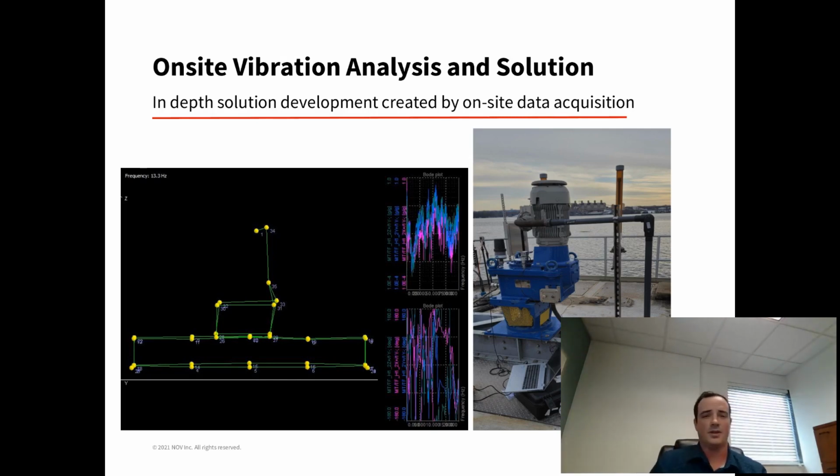So in summary here, what I want to say is it's also important to analyze your data before we leave. Oftentimes when we're at site, we'll spend a day or two gathering data and reviewing prior to leaving to ensure that we have a correct answer to what the customer's problem is, because the goal here is always to provide a correct answer to the customer. This type of data can be given to engineering firms, our own internal engineering team, and used to change or validate structures that our agitators are mounted on.